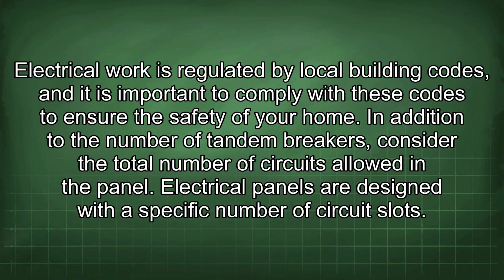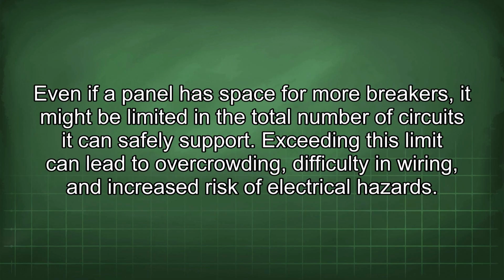In addition to the number of tandem breakers, consider the total number of circuits allowed in the panel. Electrical panels are designed with a specific number of circuit slots. Even if a panel has space for more breakers, it might be limited in the total number of circuits it can safely support. Exceeding this limit can lead to overcrowding, difficulty in wiring, and increased risk of electrical hazards.